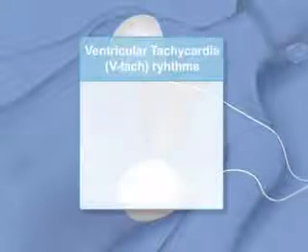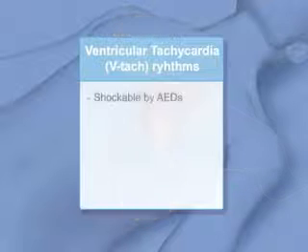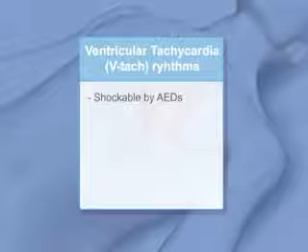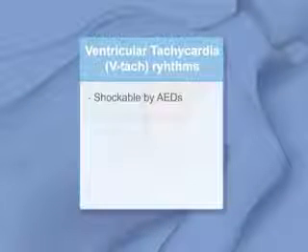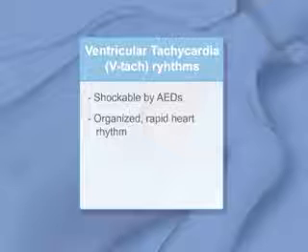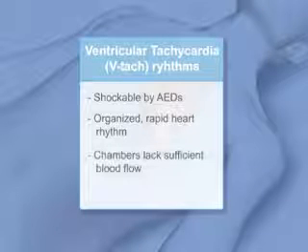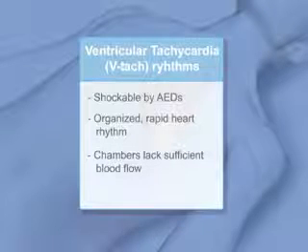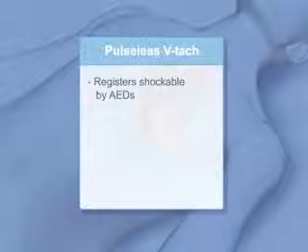AEDs are also designed to shock ventricular tachycardia, or V-tach, rhythms. The heart rhythm is organized but rapid. The heart rate does not allow the chambers to fill with enough blood to produce a sufficient blood flow. The pulseless V-tach is also considered a shockable rhythm by AEDs.